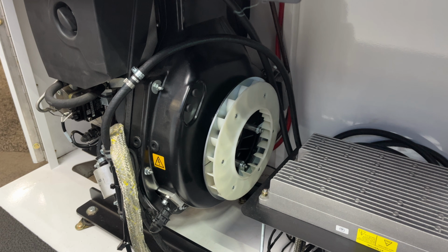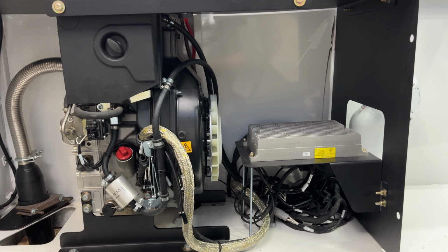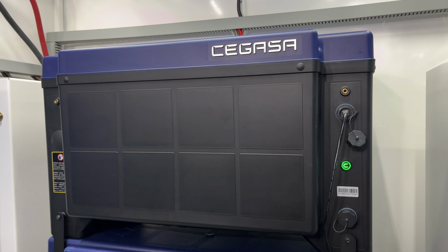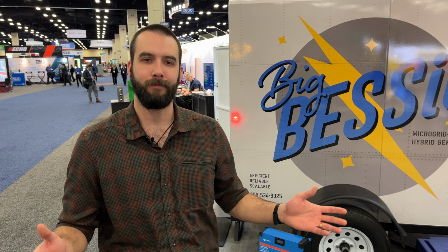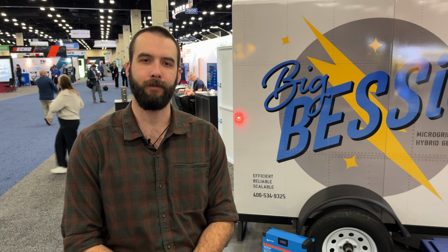The Hatz DC generator on board will produce 5 kilowatts of continuous power. It's a little single-cylinder DC diesel generator. The Cegasa batteries have about 50 kilowatt hours of usable capacity. So all in all, as it's designed in that standalone configuration, this is pretty much a one-to-one replacement for a 25 kW job site generator.